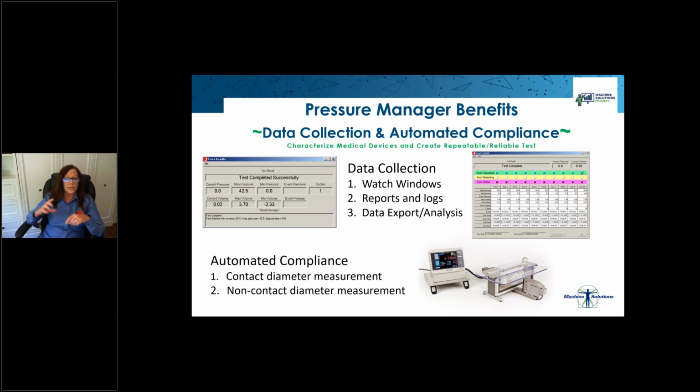Then Pressure Manager also keeps a table of the diameter measurements during testing that reports the target pressure, the actual pressure, and the micrometer reading at each step during a compliance test.